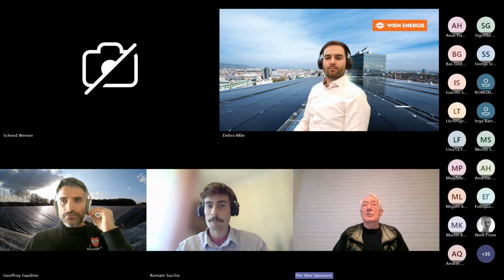But it's for Høje Taastrup, a storage of 70,000 cubic meters. If you look at the total maintenance, nearly everything has to be looked after every day, that's 240,000 Danish kroner. Then you have to add water because there's evaporation, so that's maybe 20-25% of the cost there. The main cost is the pumping cost, that's electricity for pumping. In this case, we have used 26 cycles, and if we use 26 cycles, the pumping cost will be 80%. So it's very much dependent on how you use the storage.